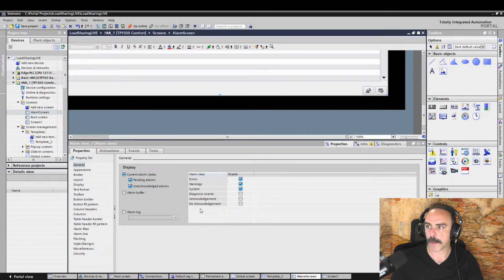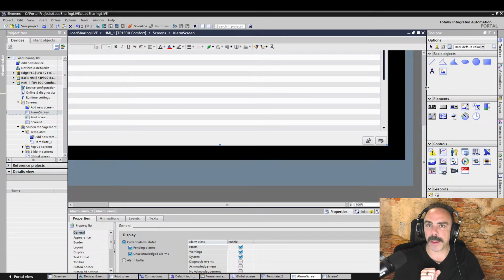So current alarms, that's just system diagnostics tied into the PLC. And you could set them up so it actually sends fault and warning information from your drives, your switches, your Ethernet switches, your remote IO racks, any of your ET200 IO - say, 'hey, I've got a wire break on this channel.' It is really awesome.